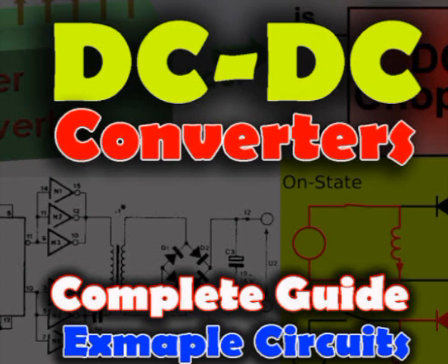This present circuit under discussion is the non-circulating type, which means that whenever you are giving signal to converter 1, of course converter 2 is in off condition, and when you are putting converter 2 into the circuit, then converter 1 has to be turned off earlier. So there is a time lag between turning on of one converter and turning off of another converter.